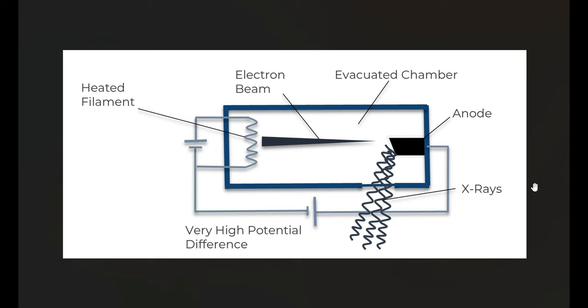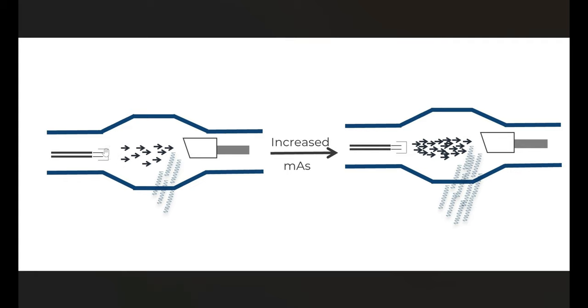Now let's talk about mAs. mAs is mA times time, and that's going to be directly proportional to the number of electrons that come off of the filament and are accelerated across the gap. If we have our x-ray tube with electrons moving across towards our anode, we produce a certain number of x-rays with a certain number of electrons. If we increase the mAs, we increase the number of electrons — not how penetrating or how energetic they are, remember that's KV — but we increase the actual number of electrons, which increases the number of x-rays.